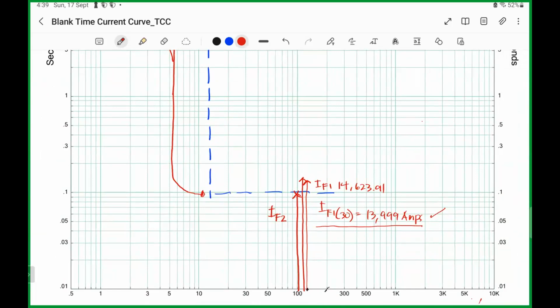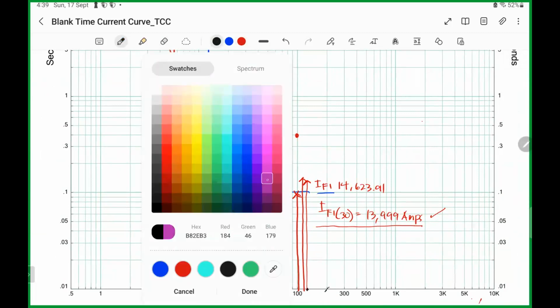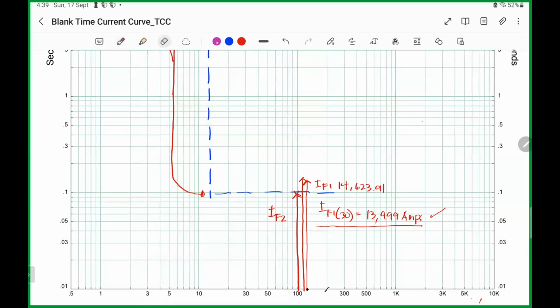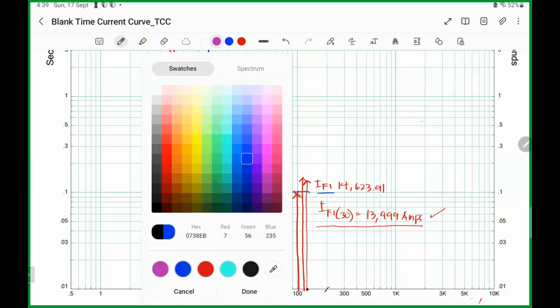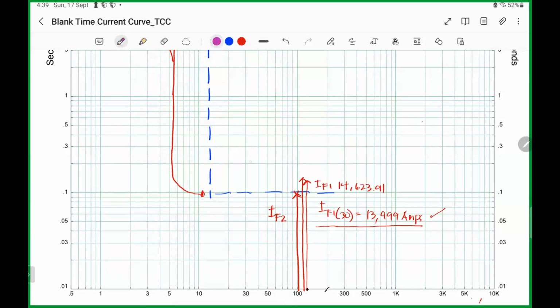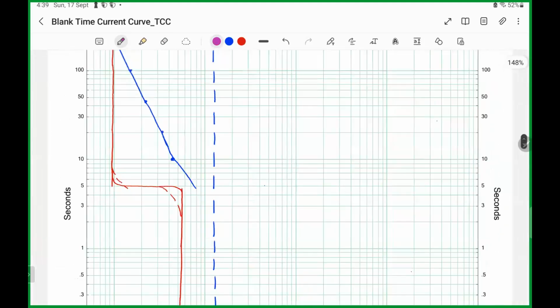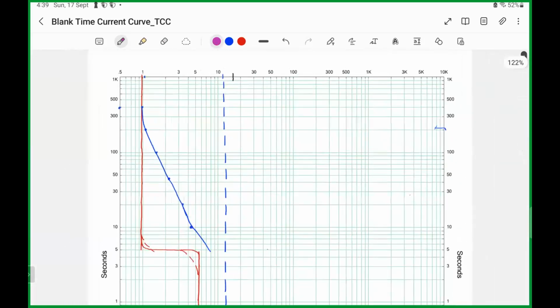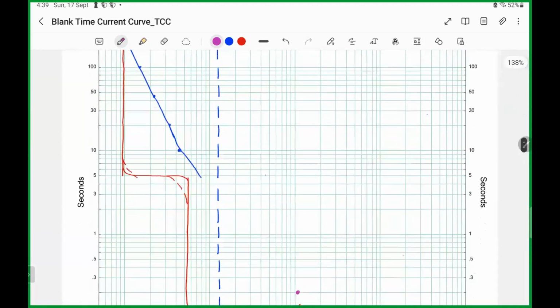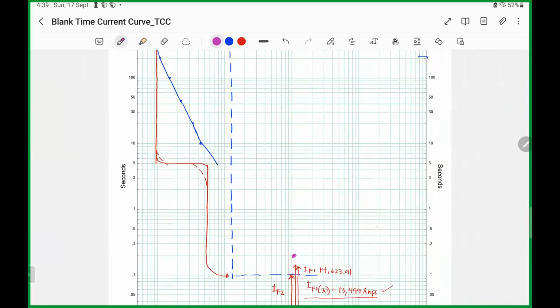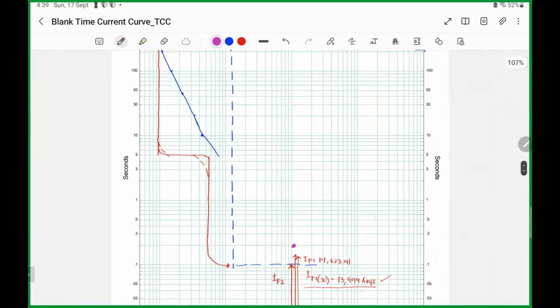So I can trip this one around, I set it in the electronic trip unit at 0.4 seconds. So let me find the 0.4. This one somewhere here. Let's change the color. Wait. Point 4. So this, sorry, 0.4. So, there. So the long time, we have the continuous for the low voltage circuit breaker. We have the short time pickup. Okay? So that is my current, which is the minimum fault reference of 13,999.